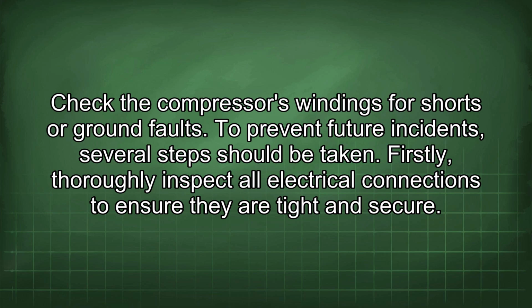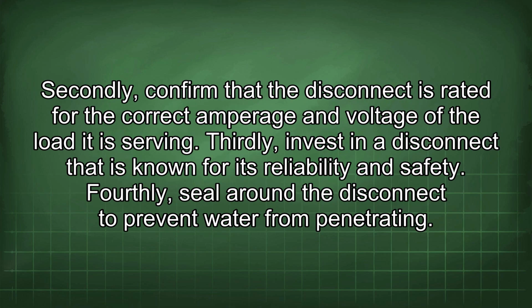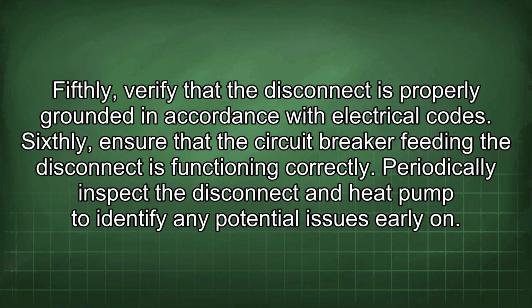To prevent future incidents, several steps should be taken. Firstly, thoroughly inspect all electrical connections to ensure they are tight and secure. Secondly, confirm that the disconnect is rated for the correct amperage and voltage of the load it is serving. Thirdly, invest in a disconnect that is known for its reliability and safety. Fourthly, seal around the disconnect to prevent water from penetrating. Fifthly, verify that the disconnect is properly grounded in accordance with electrical codes. Sixthly, ensure that the circuit breaker feeding the disconnect is functioning correctly.